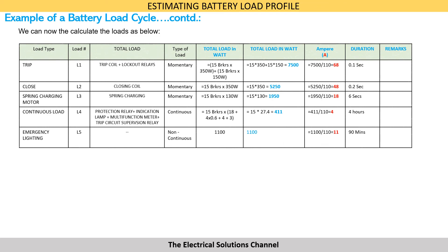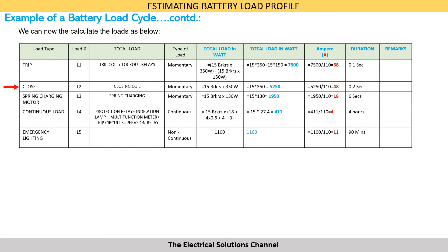The load during tripping of the breakers will be the trip coil load plus the burden of all the lockout relays. This is a momentary load, and the total load during tripping in our example works out as 7,500 watts, giving approximately 68 amps during tripping. We can similarly calculate the DC loads for closing operation and spring charging conditions.